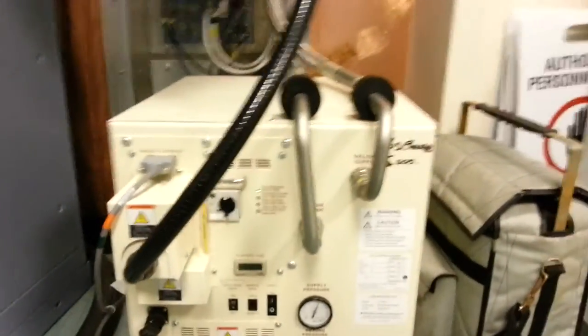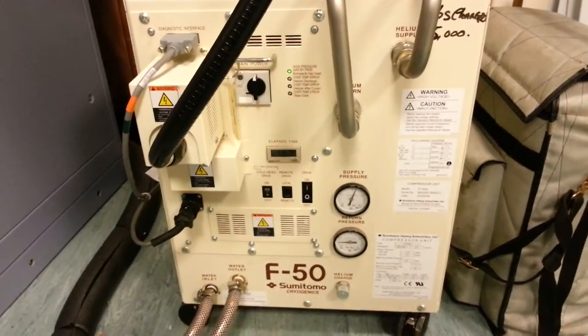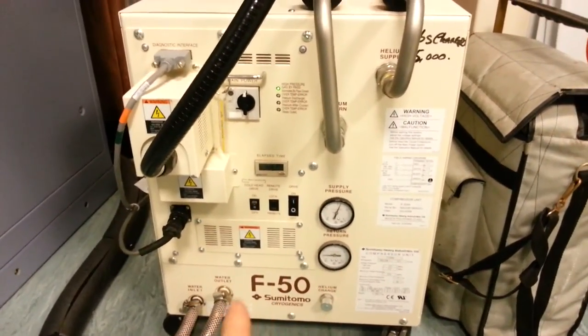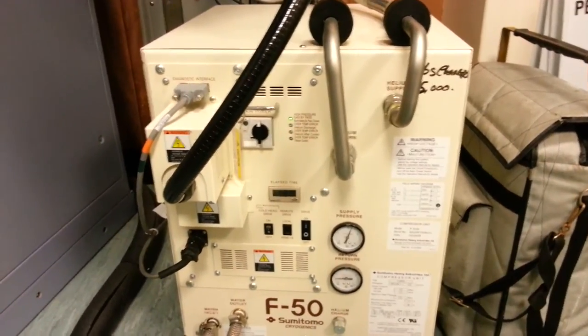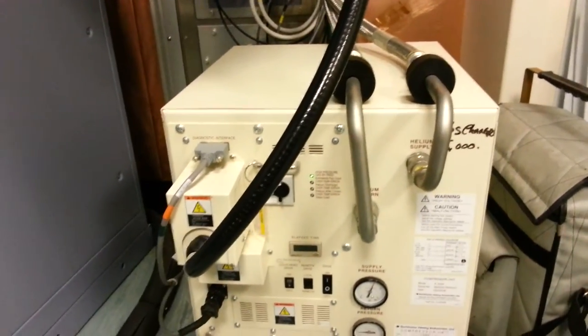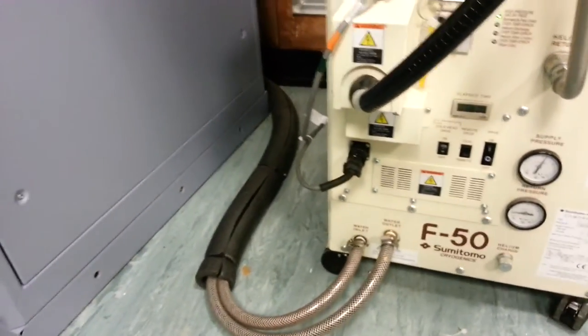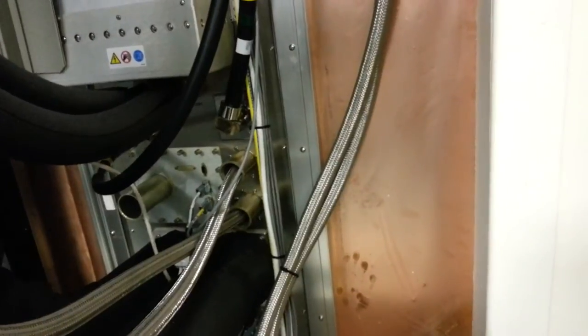And I'll explain how that works. But in this case it's used because we're looking for a very low temperature — in this case 4 Kelvin, that's minus 269 Celsius. And it has a cooling power of 1 Watt. That's right, 1 Watt of cooling at minus 269 Celsius. And it uses this 10 horsepower scroll compressor to run it, and it takes several gallons a minute of chilled water to evacuate the heat. So it's not particularly efficient. And I'll draw you a diagram of how the Gifford-McMahon system works later.